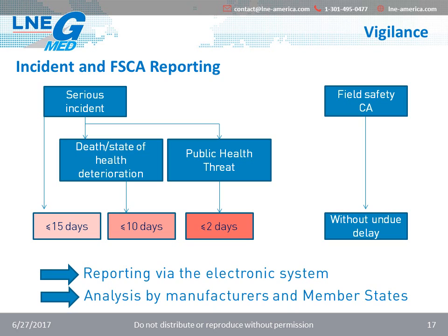As a general rule, the manufacturer shall report any serious incident involving devices made available on the Union market, except expected side effects which are clearly documented in the product information and quantified in the technical documentation and are subject to trend reporting, as well as any field safety corrective actions for devices made available on the European Union market, including in some cases field safety corrective actions undertaken in a third country in relation to a device which is also legally made available in Europe.